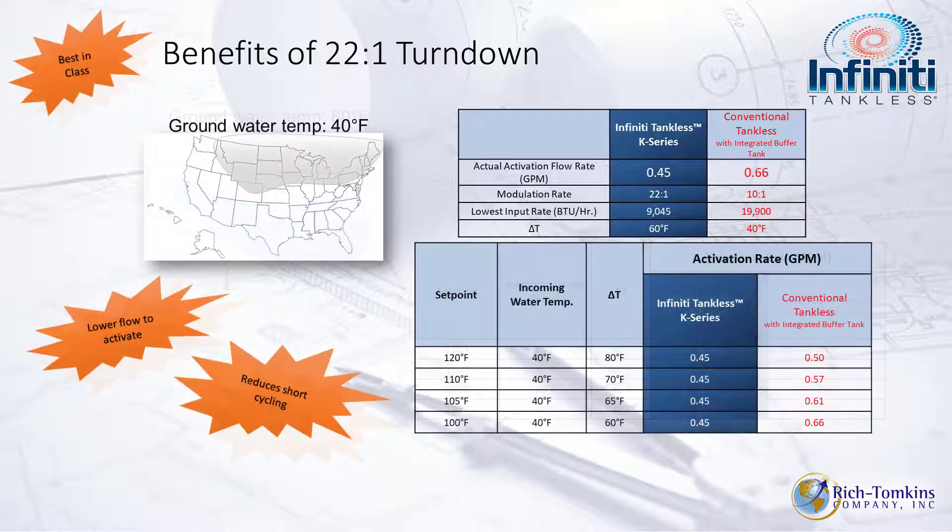In northern climates, nothing changes for the Infiniti K — 0.45 GPM activation across all Delta T's from 60 up to 80 degrees. Comparing to a conventional tankless with a buffer tank, you're looking at activation rates from 0.66 down to 0.5 GPM with fluctuating temperatures and potential cold water sandwich. That 22 to 1 turndown ratio is best in the business.